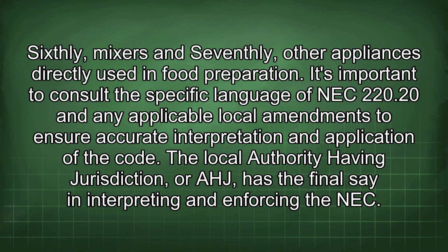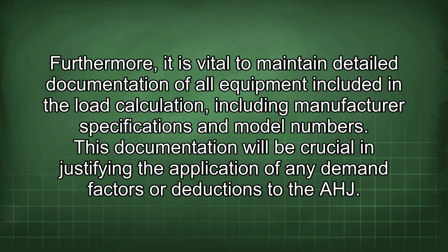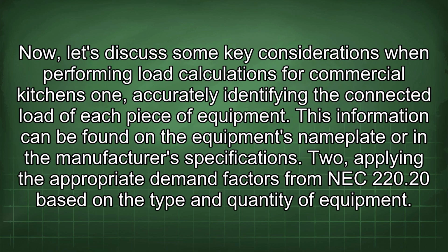It's important to consult the specific language of NEC 220.20 and any applicable local amendments to ensure accurate interpretation and application of the code. The local authority having jurisdiction, or AHJ, has the final say in interpreting and enforcing the NEC. Furthermore, it is vital to maintain detailed documentation of all equipment included in the load calculation, including manufacturer specifications and model numbers. This documentation will be crucial in justifying the application of any demand factors or deductions to the AHJ. Now, let's discuss some key considerations when performing load calculations for commercial kitchens.